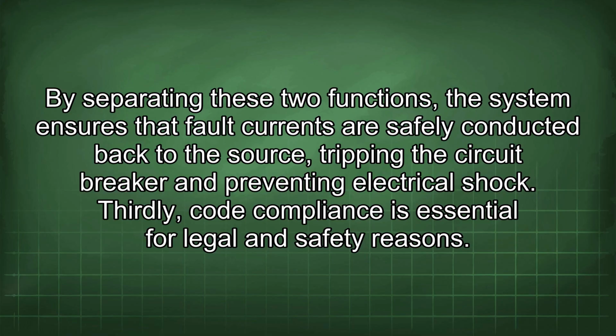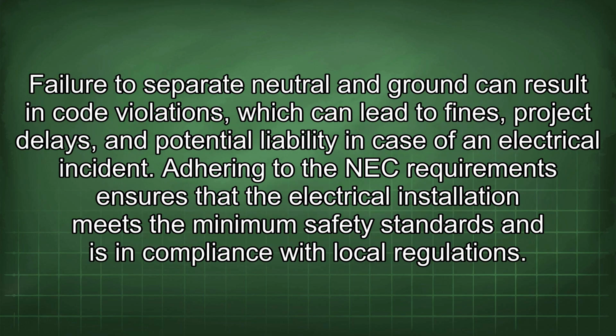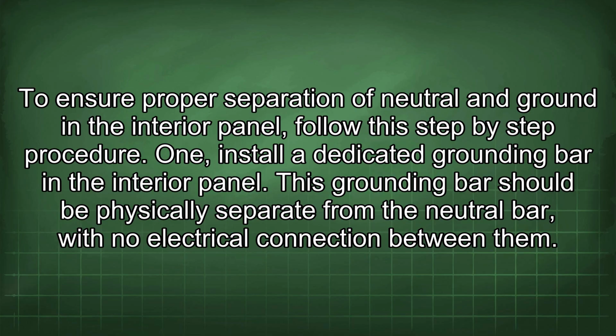Thirdly, code compliance is essential for legal and safety reasons. Failure to separate neutral and ground can result in code violations, which can lead to fines, project delays, and potential liability in case of an electrical incident. Adhering to the NEC requirements ensures that the electrical installation meets the minimum safety standards and is in compliance with local regulation. To ensure proper separation of neutral and ground in the interior panel, follow this step-by-step procedure.